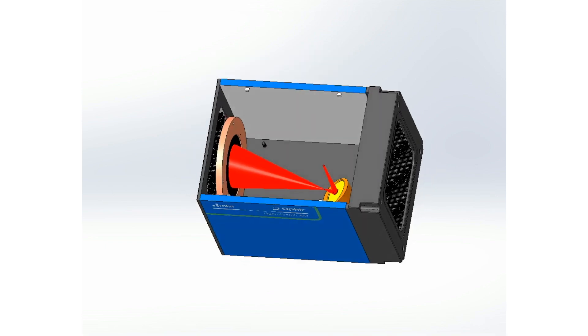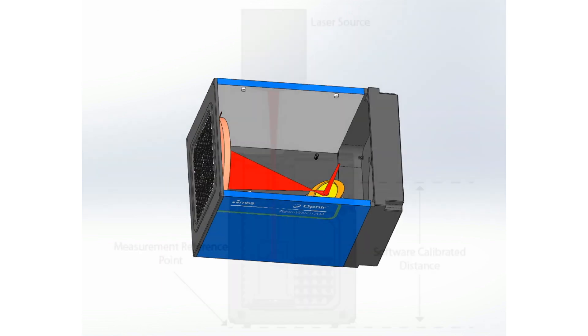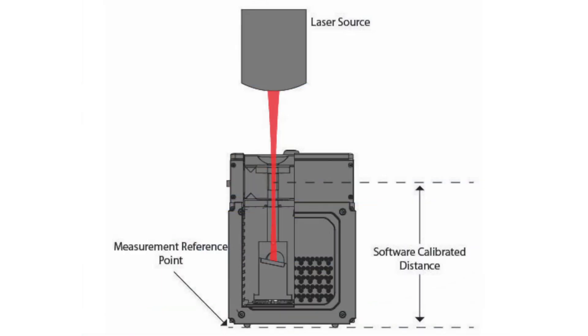The lower section contains the NIST traceable power sensor. The power sensor can measure up to 1 kilowatt for 2 minutes without the need for water cooling.